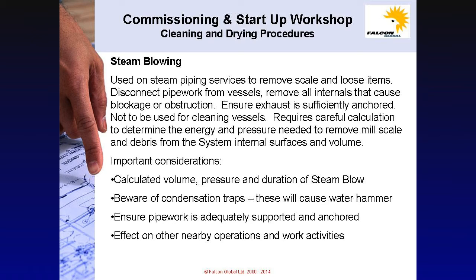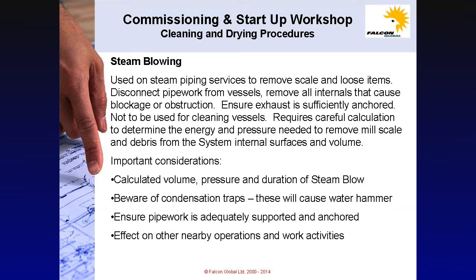Steam blowing is not to be used for cleaning vessels. It requires careful calculation to determine the energy and pressure needed to remove mill scale and debris from the system's internal surfaces. Important considerations are careful calculation of the volume, pressure and duration of each steam blow. Beware of condensation traps. These will cause water hammer and could damage the pipework. Ensure pipework is therefore sufficiently anchored and properly supported. Beware of the impact on other nearby operations and work activities and neighbouring communities.